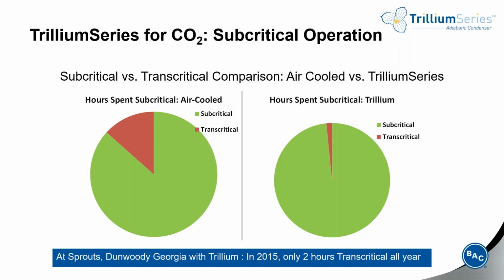Where adiabatic cooling really shines in terms of CO2 use is with subcritical operation. Here's a graphical representation of a Sprouts Market in Georgia, where when they switched to an adiabatic gas cooler, after 1 full year of operation, they found that they ran transcritical only 2 hours out of the year. With the CO2 system, whenever you're running transcritical, you're using much more compressor energy. Keeping the system operating subcritical is always the goal.